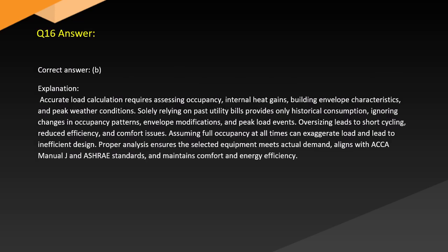Answer. Correct answer, B. Explanation. Accurate load calculation requires assessing occupancy, internal heat gains, building envelope characteristics, and peak weather conditions. Solely relying on past utility bills provides only historical consumption, ignoring changes in occupancy patterns, envelope modifications, and peak load events. Oversizing leads to short cycling, reduced efficiency, and comfort issues. Assuming full occupancy at all times can exaggerate load and lead to inefficient design. Proper analysis ensures the selected equipment meets actual demand, aligns with the ACCA Manual J and ASHRAE standards, and maintains comfort and energy efficiency.